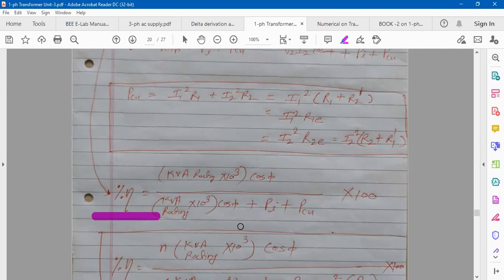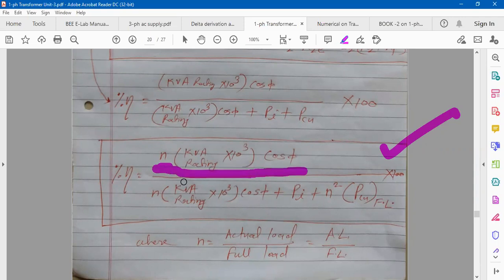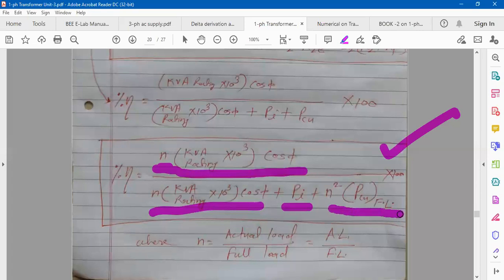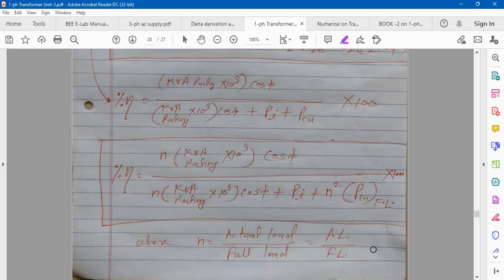For such conditions — whenever you get asked to calculate efficiency at any percentage of load — this is the general formula to use: N into KVA rating into 10³ cosφ, divided by the same parameter plus iron loss plus N² times full load copper loss. Here N is the ratio of actual load upon full load.